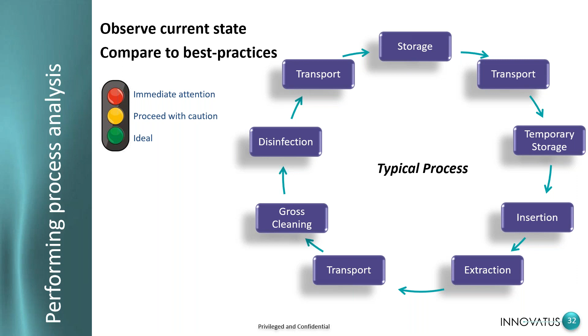So we're going to look at all the different phases of the usage cycle of a TEE probe and what needs to be fixed immediately, what is kind of an okay process, and then what's ideal. So how are probes stored? Within a bin, drawer, or placed on a shelf. That is red. We want to immediately change that. A bin is fine for transport because it's a short period of time, but we do not want to leave the probe coiled for an extended period of time.